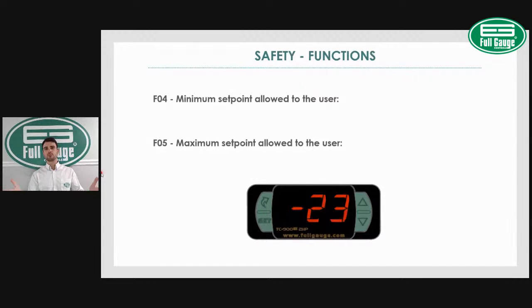Sometimes customers don't know that a cooler cannot be a freezer, and they want to set that temperature down to 10 degrees. What will happen? My compressor will run continuously. I will never reach that 10 degrees with a cooler, and I'll get a failure. So in order to prevent those failures, you can actually set a minimum and maximum set point threshold.